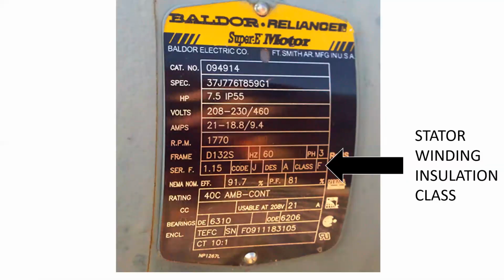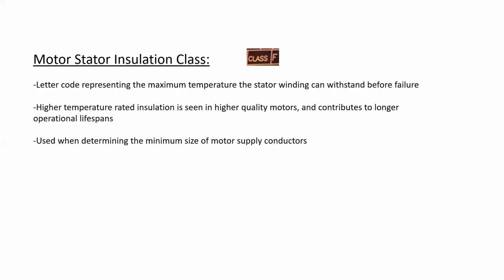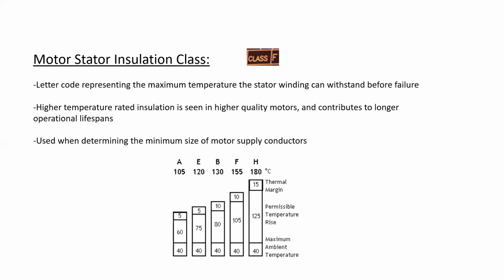Stator winding insulation class. This motor has a Class F stator winding insulation. The stator insulation class is a letter code representing the maximum temperature the stator winding can withstand before we start to see failure. Higher temperature rated insulation is seen in higher quality motors and contributes to a much longer operational lifespan. These are used when determining the minimum size of supply conductors, as per Section 28 of the Canadian Electrical Code. There are 5 different classifications of stator insulation.